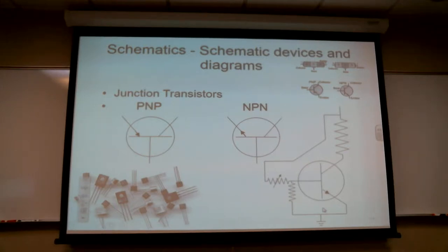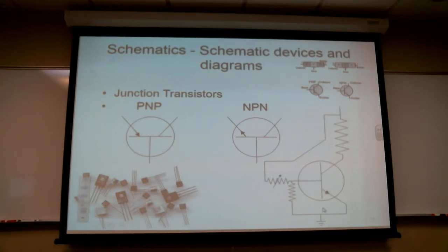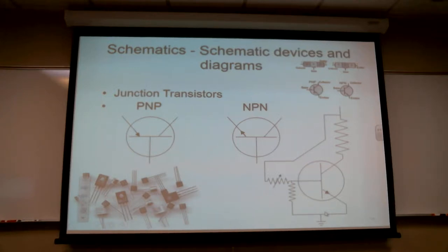The load has a partial short in it, somebody hooked a battery in backwards, something was done wrong. Output transistors are pretty robust — they typically do not fail on their own. So if you find yourself with blown-out output transistors, be cautious, because if you throw a new box in there, you might be buying another one.